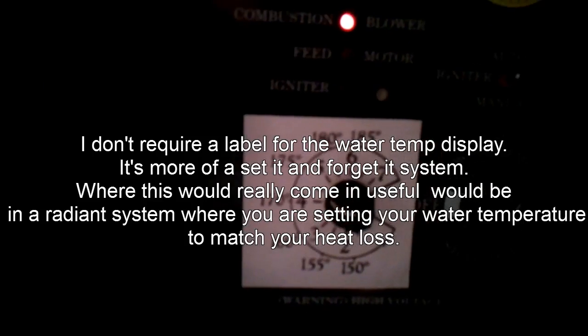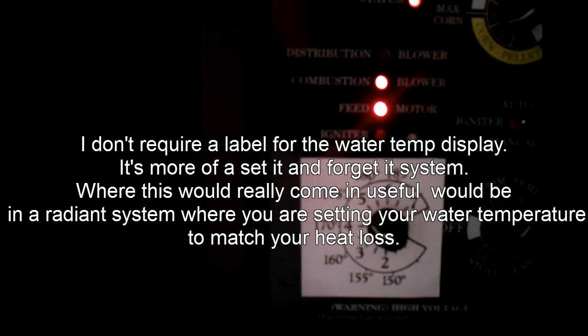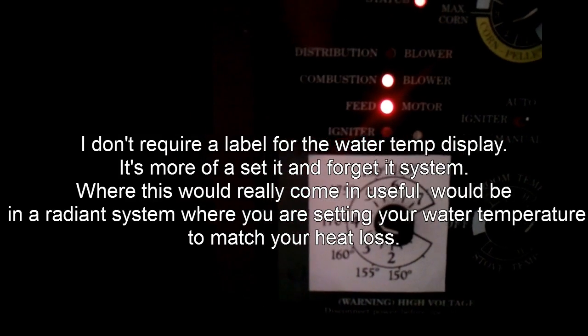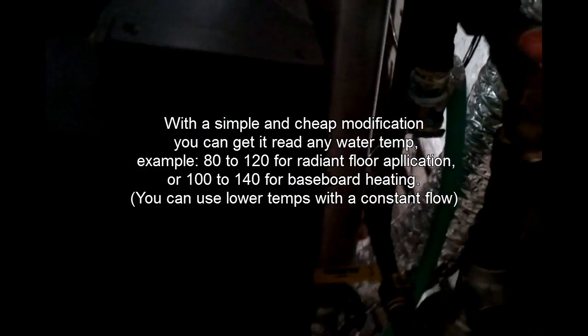And as far as shutting the stove down, there's three ways that this stove will shut off. One is through the room sensor. This particular stove uses a room sensor, and with a 25-cent modification, it's now set to read water temperature instead of air, and I've got it set at 170. So if the water would get above 170 degrees, the stove would shut off. Also, there's a thermostat in line with that, so I could shut the stove off and on from upstairs.